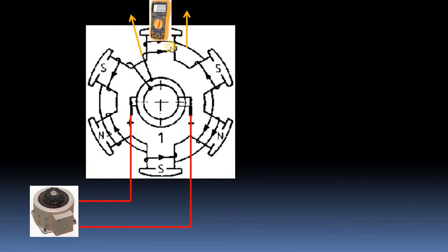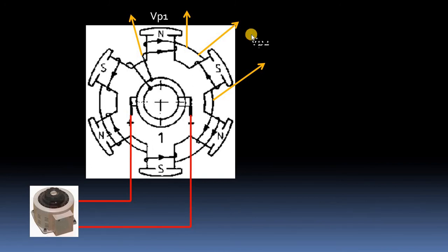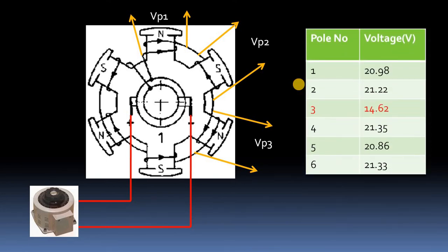I apply the voltage with the variac and measure the voltage across each pole using a multimeter. Voltage across pole one is VP1, pole two is VP2, pole three is VP3, and so on for all six poles. The readings I got are: pole 1 = 20.98 V, pole 2 = 21.22 V, pole 3 = 14.62 V, pole 4 = 21.35 V, pole 5 = 20.86 V, pole 6 = 21.33 V. The average of the six voltages is 20 volts.